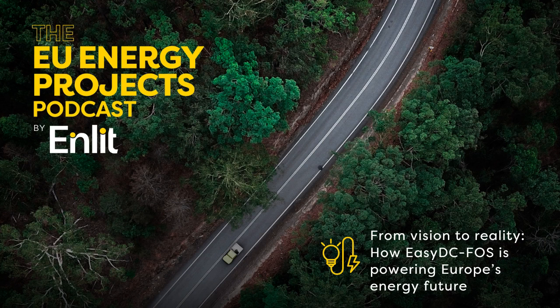Then you have the impact of faults. Today, finding a fault in an HVDC line is not easy. Short circuit levels in an HVDC line are around 2,000 amps, compared to AC where it's 40,000 to 200,000 amps. So detecting a short circuit in an AC cable is much easier because of its very high amp short circuit level, whereas in a DC cable this happens at much lower amps, making it much more difficult to detect.